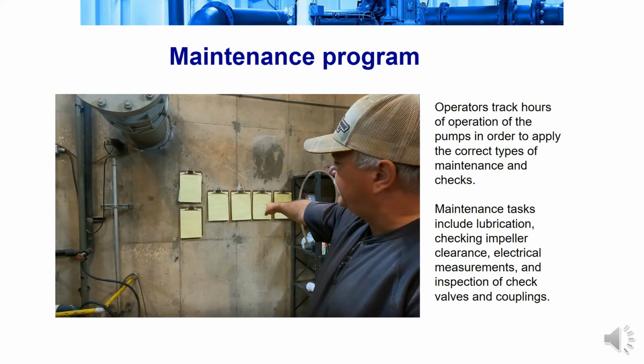The Portage lift station has a maintenance program that they keep track of using several clipboards like these on the wall. The clipboards have the hours and what sort of maintenance was done on those pumps, so that any operator can go to the clipboard for the specific device and ensure that that piece of equipment is up to maintenance standards and has not been overdue for any sort of maintenance. Some maintenance tasks that are common for these systems include lubrication, checking the impeller clearances, electrical measurements, and inspection of check valves and couplings.